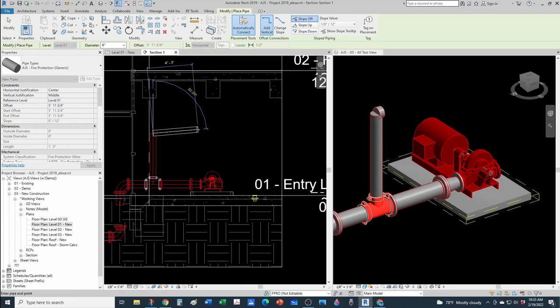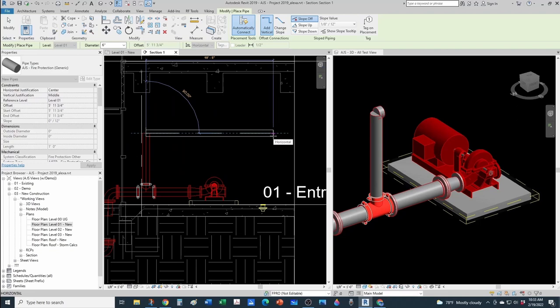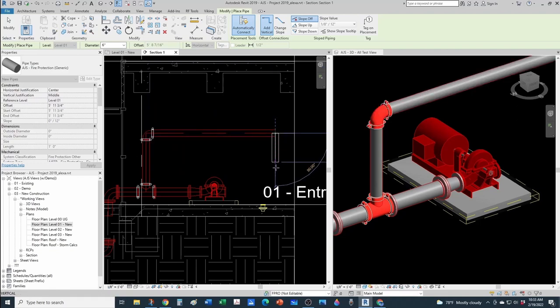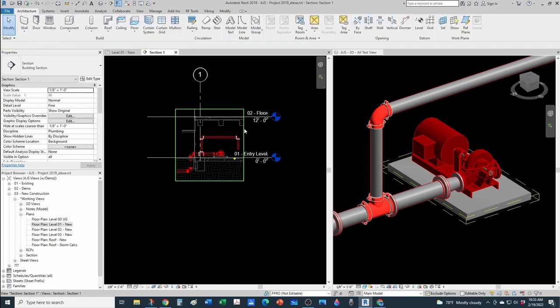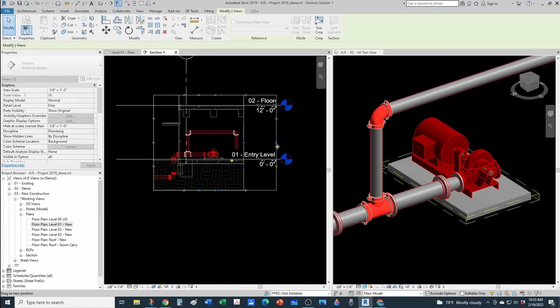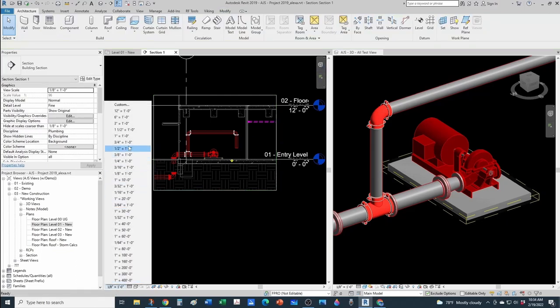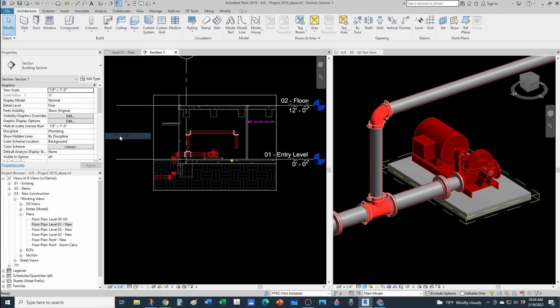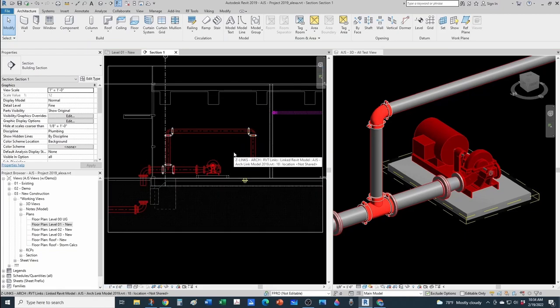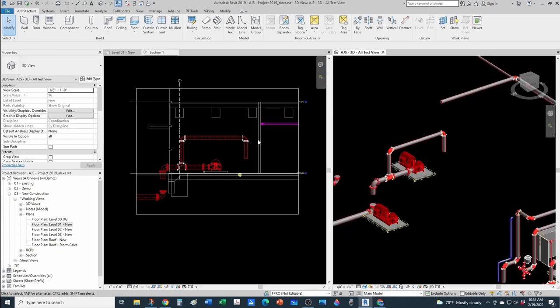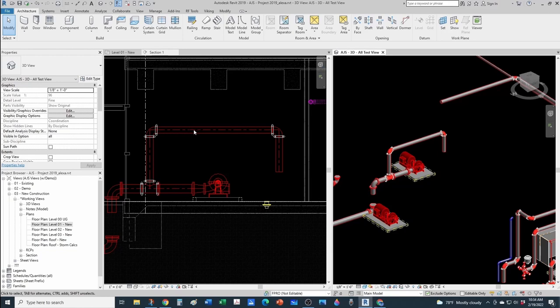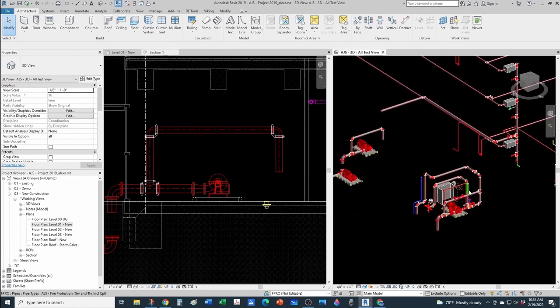And you can adjust the elevation of that bypass a little later. For now, let's just create it. I'm gonna extend my section a little bit, and it's always a good idea to overspace things at the beginning, so you're not struggling with your pipes and fittings and pipe accessories, and then you shorten your design to be more space efficient. On your bypass, you're gonna need an isolation valve, a check valve, and another isolation valve, so that your check valve is isolated on both sides, and whatever type of maintenance you want to do, you can do it right there.